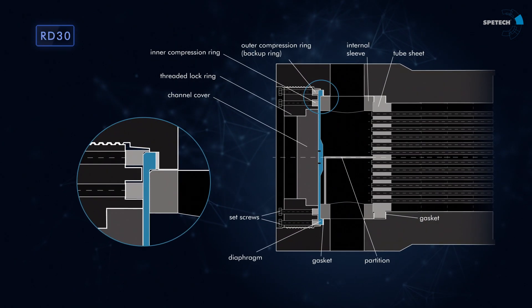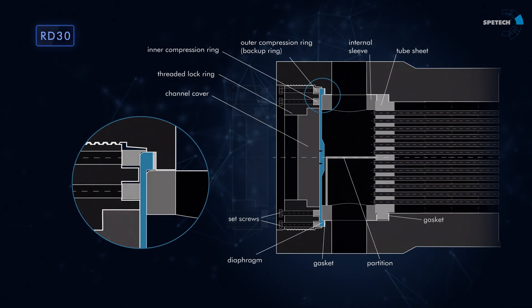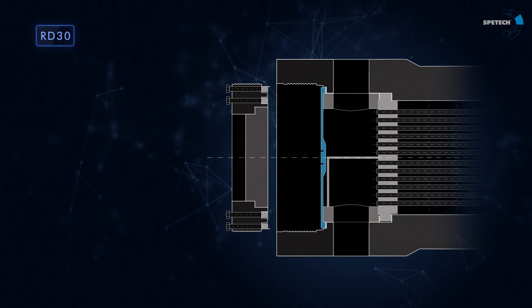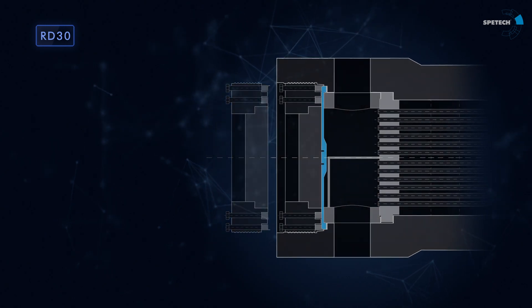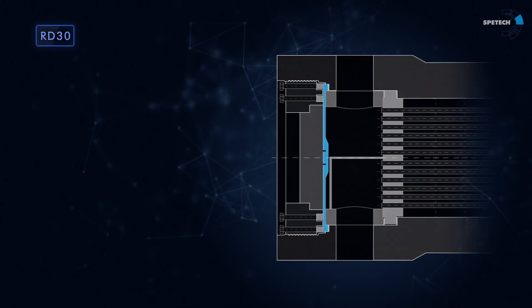A special group of diaphragms are domes used in heat exchangers with screwed covers. The basic element of such sealing system is metal diaphragm closure installed together with auxiliary soft metal gasket formed by a system of pressuring and blocking rings.